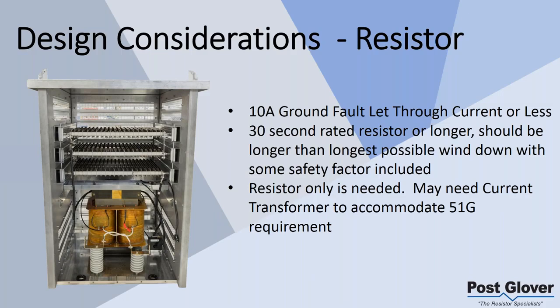Keep in mind that if you have multiple parallel generators, you're going to want to keep that total current down. You may have your own idea. I would say 1500 amps. Some people say 1000, depending on what your goals are. But try to keep it down as much as you can if you have parallel LRGs. But the point is you're going to be using a 10-second, 200 or 400 amp typically resistor. And that's the low resistance ground.